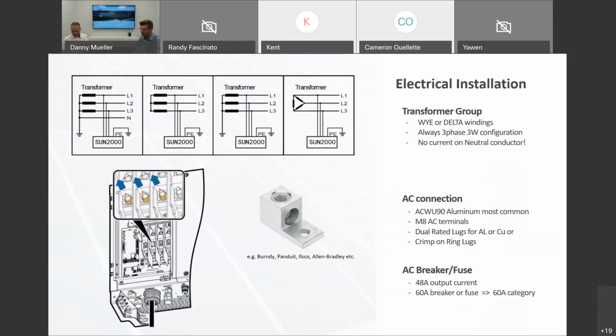But no matter if you have a neutral or not, the inverter will not use the neutral as a current carrying conductor. And that is not very important for very small systems, but if you have extremely large systems or bigger commercial systems, it is definitely a cost saving if you can run a 3-conductor plus ground ACWU cable, for example, instead of having all the 4 conductors in your cable when it's not even utilized by the inverter.